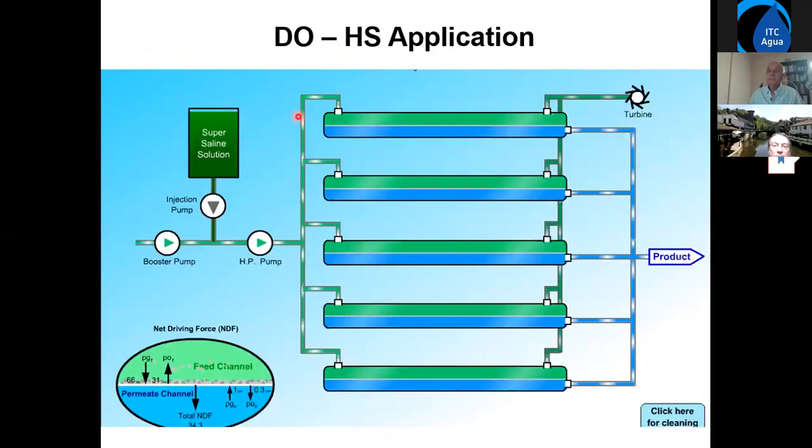The reason is you need a very high pressure pump, higher pressure than here. Everything has to be made of corrosion resistant stainless steel. It's expensive, but in the system which was implemented, it worked very well.